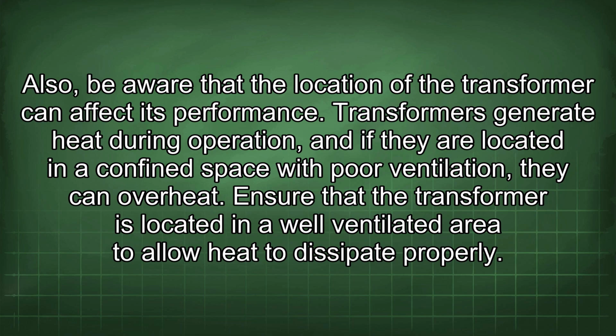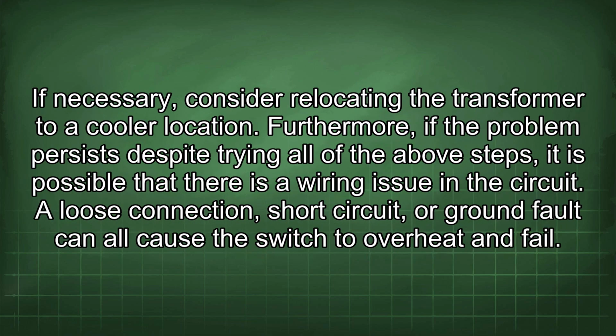Also, be aware that the location of the transformer can affect its performance. Transformers generate heat during operation, and if they are located in a confined space with poor ventilation, they can overheat. Ensure that the transformer is located in a well-ventilated area to allow heat to dissipate properly. If necessary, consider relocating the transformer to a cooler location.